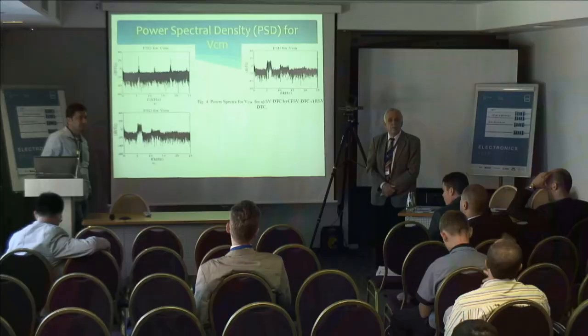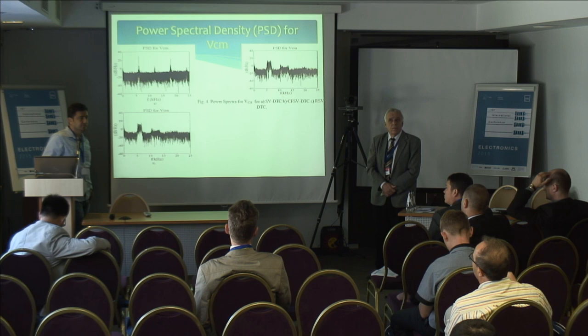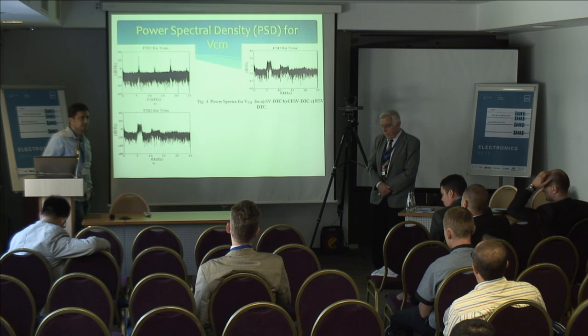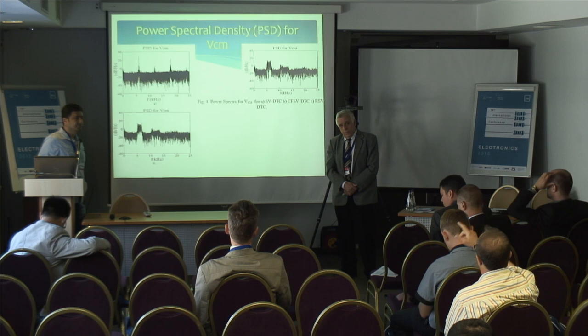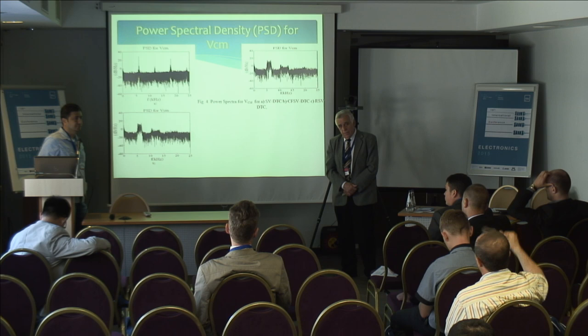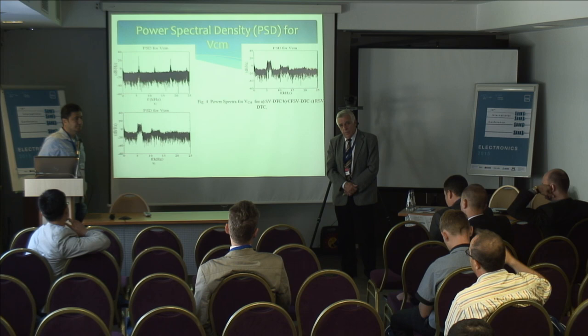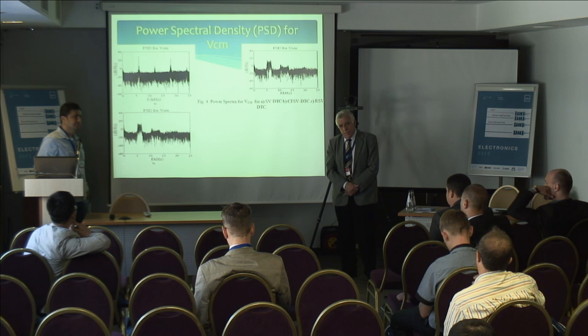There are standards for AC drivers or any electronic equipment. I think it is good to look at the megahertz range to see the electromagnetic interference and meet the standards. But as far as I can see here, we look at only the harmonics. I was expecting the megahertz-level frequency to be higher here, maybe 400 kilohertz to megahertz, to see the interference with the grid. And then after that, we can say whether this driver requires an EMI filter or not.